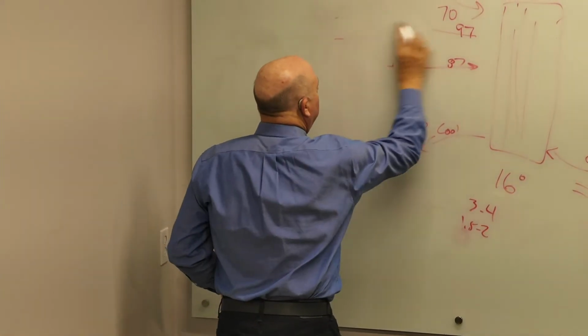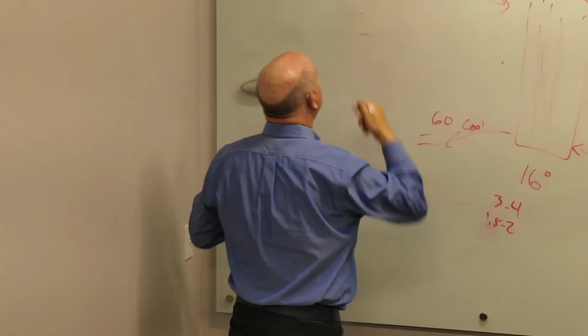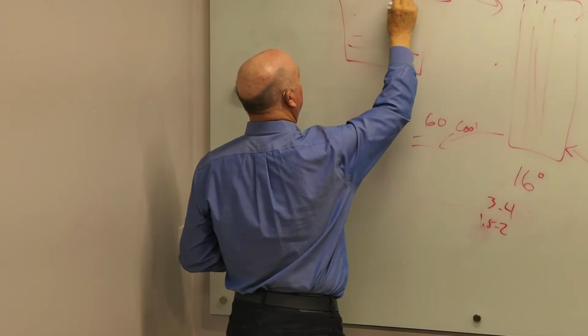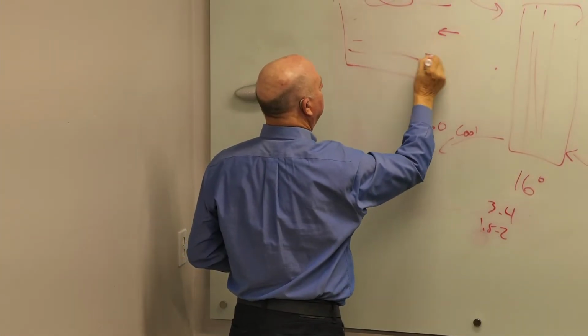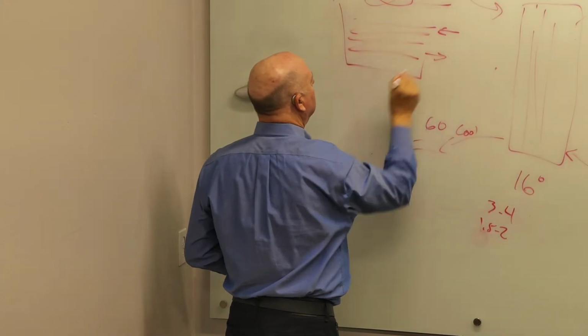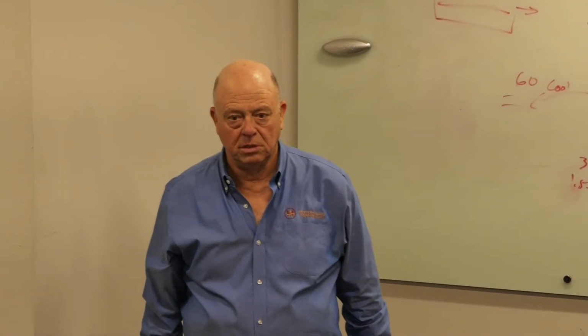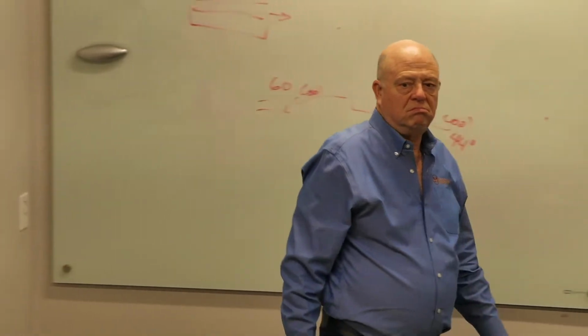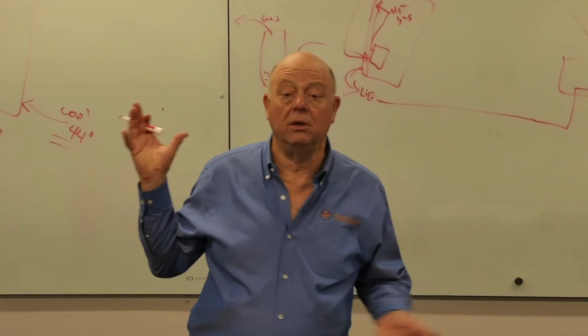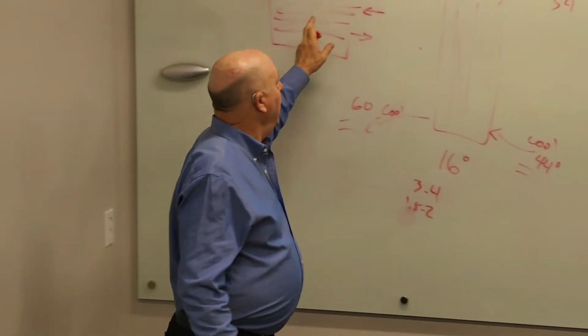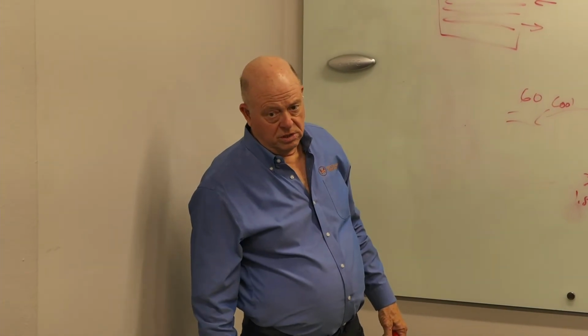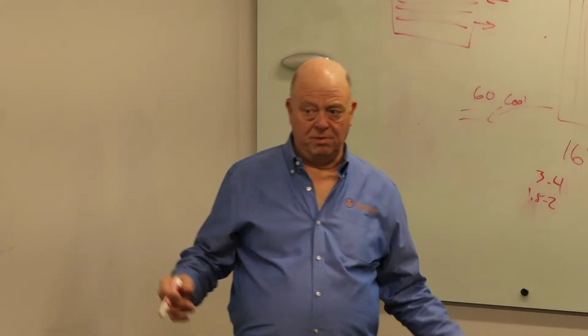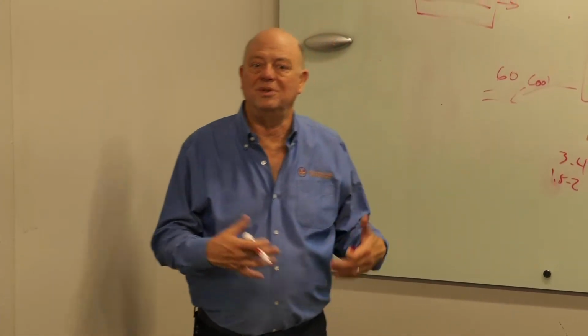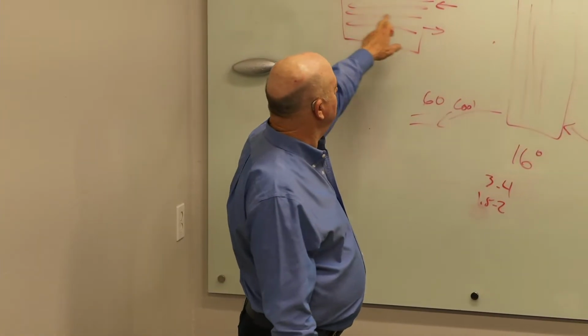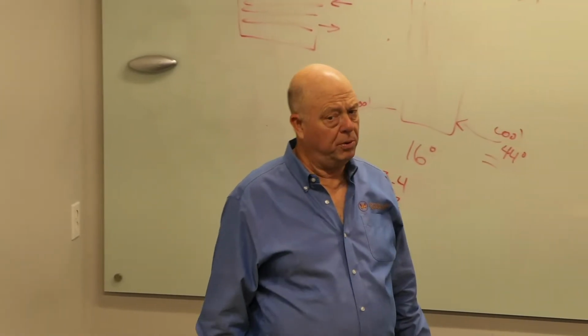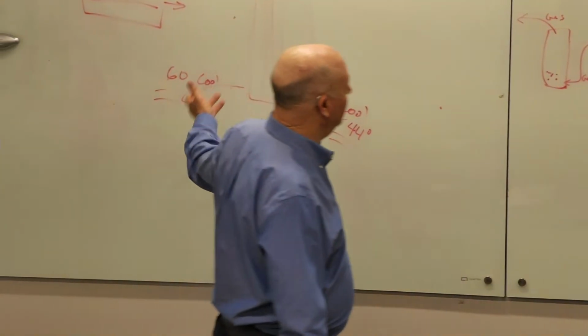The alternative is, instead of doing that, you use a fluid cooler. And a fluid cooler is a cooling tower. It's got a heat exchanger built right into it with a bunch of passes. And the water just comes down over that heat exchanger. One of these probably weighs 4 times what a cooling tower weighs. That might be a big deal on a roof. And the approach is not nearly as good. So you have to oversize them to try to get equivalent performance, and that's another reason they're bigger and more expensive. But these are tubes, water going through tubes. They don't plug up. They're pretty bulletproof. So we prefer fluid coolers.